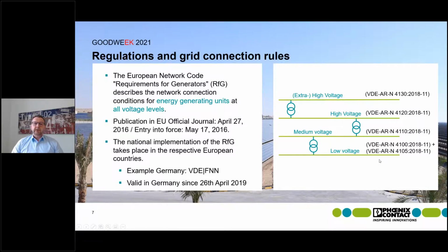For the low voltage level, that's VDE AR guideline 4100 and 4105. For medium voltage, from 10 to 60 kilovolt, that's VDE AR 4110. For high voltage, 110 kilovolt, there's guideline 4120, and for high voltage above 220 and 380 kilovolt, guideline 4130. So these European grid code regulations are derived into 5 different German guidelines.